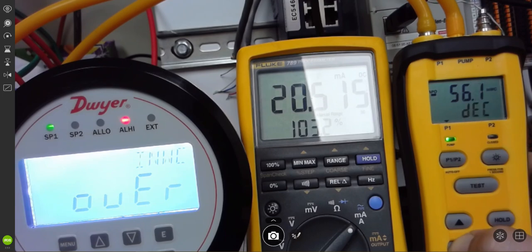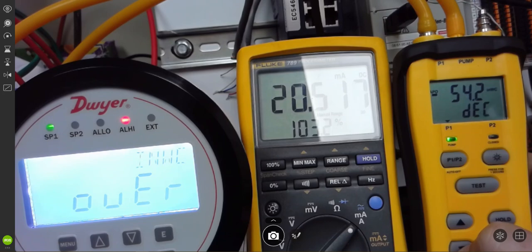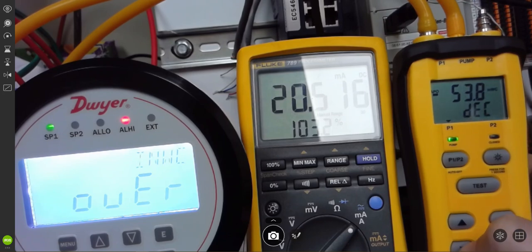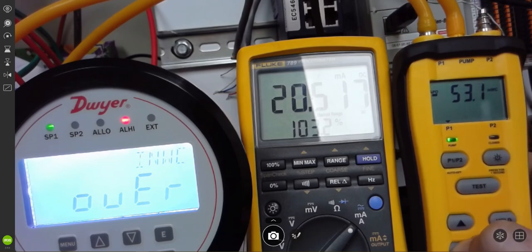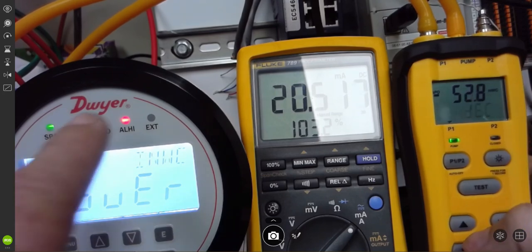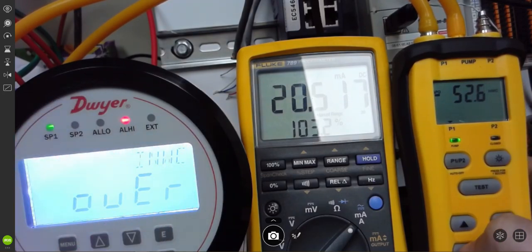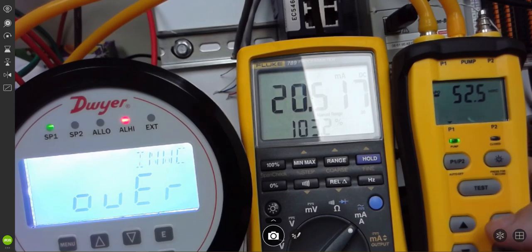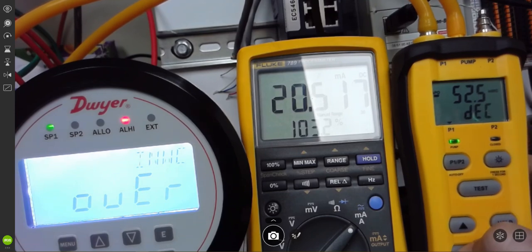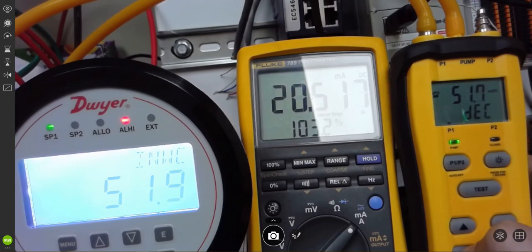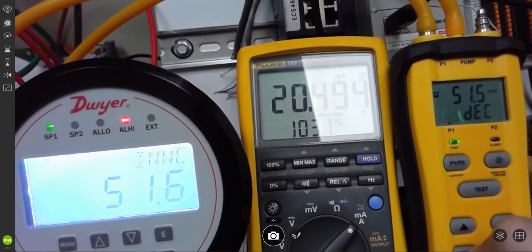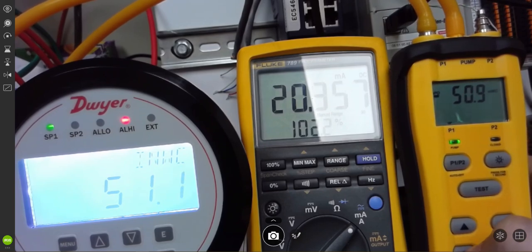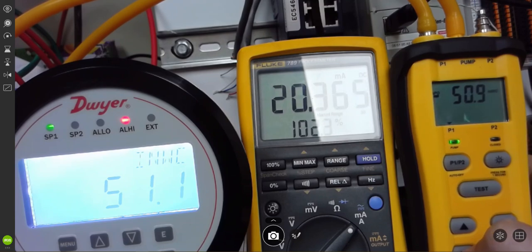We're not using any of these alarm functions on the line that I'm aware of. We're simply recording these values through pinpoint. So we don't use alarm high or set point one. Whatever you see there is just the default that was programmed and ignore it. If you see any of these indicators, the only thing we care about is the thing's lit up. We don't care about set points or alarms. If we do any alarming, that will be done in the PLC, not in the instrument. Let's get that thing back down. Now, once you get close, you can just start tapping it one at a time and just wait a second for it to settle in because it will get there. It'll at least get within point one.